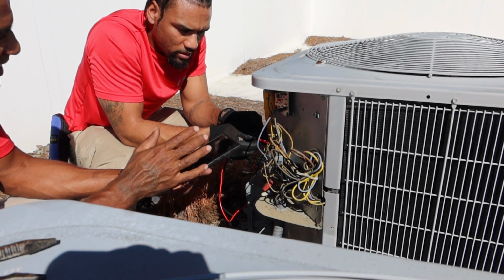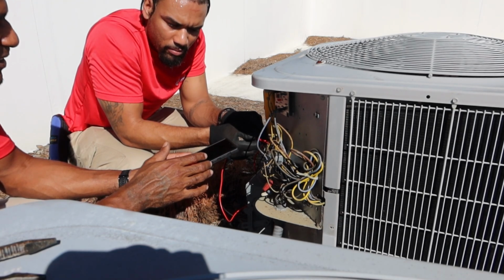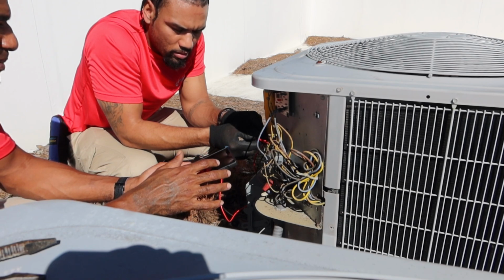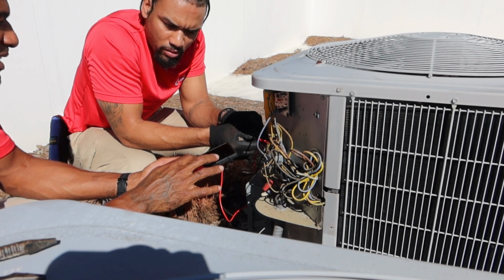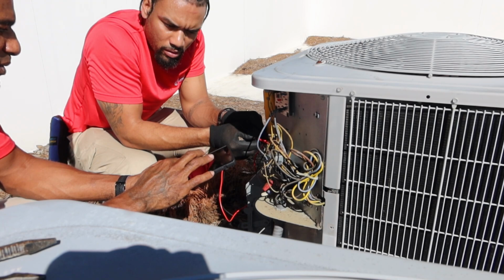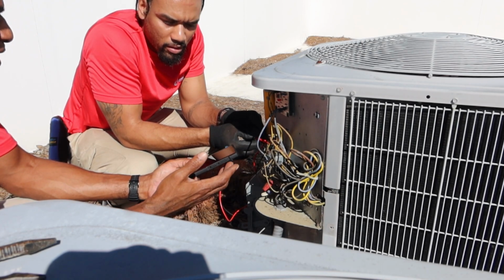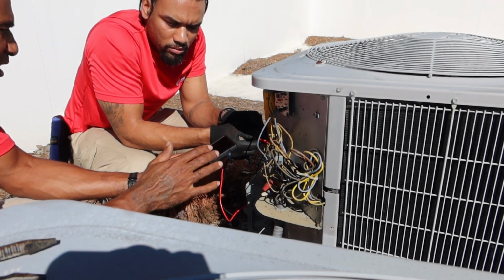So that capacitor is not within ratings, but some people, we're gonna let them make it on this. This is our planned customer. Because some people say we can do plus or minus 10%. So we do 10%, anything lower than 4.5. Okay, all right. So that's how we're gonna do on our maintenance. We'll go ahead and do 4.5.